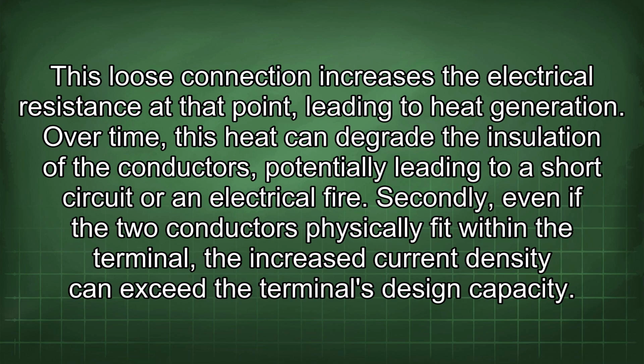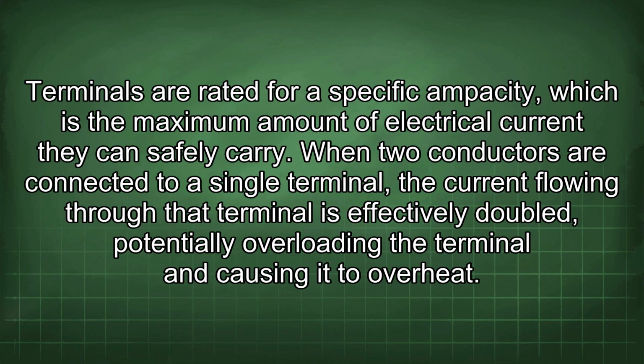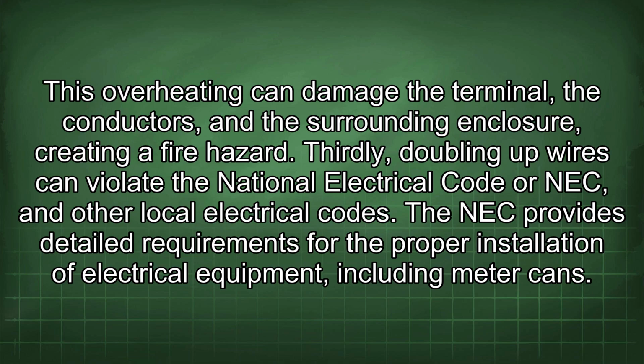Over time, this heat can degrade the insulation of the conductors, potentially leading to a short circuit or an electrical fire. Secondly, even if the two conductors physically fit within the terminal, the increased current density can exceed the terminal's design capacity. Terminals are rated for a specific ampacity, which is the maximum amount of electrical current they can safely carry. When two conductors are connected to a single terminal, the current flowing through that terminal is effectively doubled, potentially overloading the terminal and causing it to overheat. This overheating can damage the terminal, the conductors, and the surrounding enclosure, creating a fire hazard.